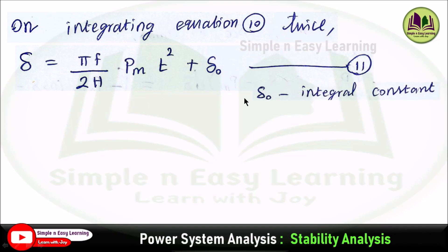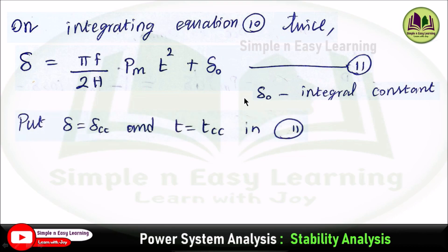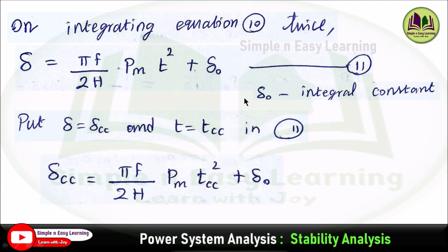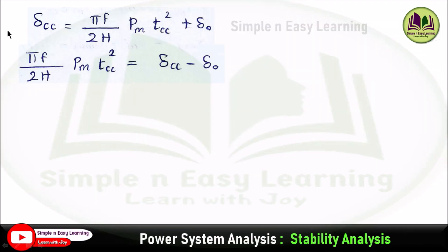Here, delta_0 is the integration constant. Now, substituting delta equal to delta_cc and t equal to t_cc, where delta_cc is the critical clearing angle and t_cc is the critical clearing time. From there we get delta_cc equal to pi f divided by 2h into P_m times t_cc squared plus delta_0. Bringing delta_0 to the other side gives delta_cc minus delta_0, and solving for t_cc squared gives: t_cc squared equals (delta_cc minus delta_0) divided by (pi f P_m divided by 2h).